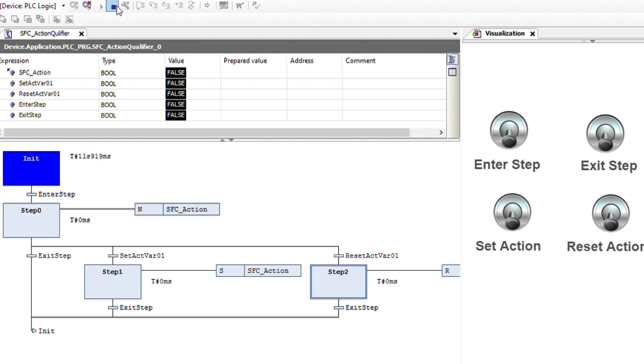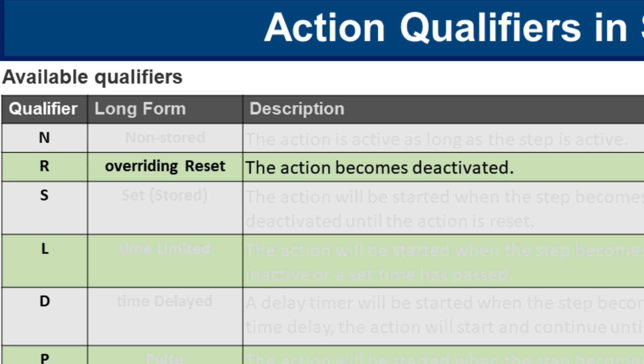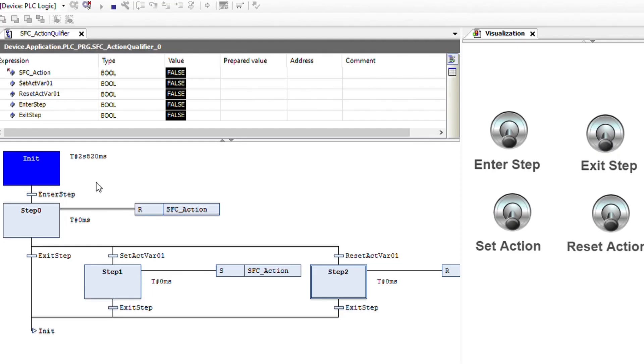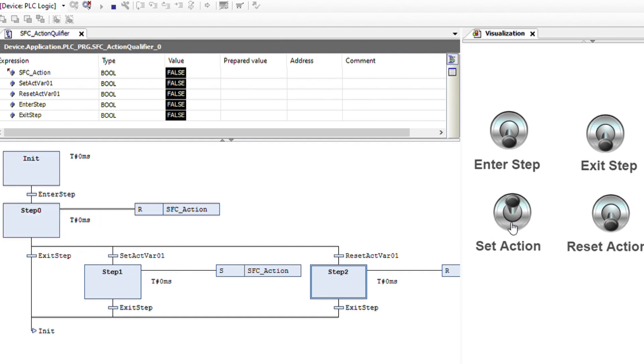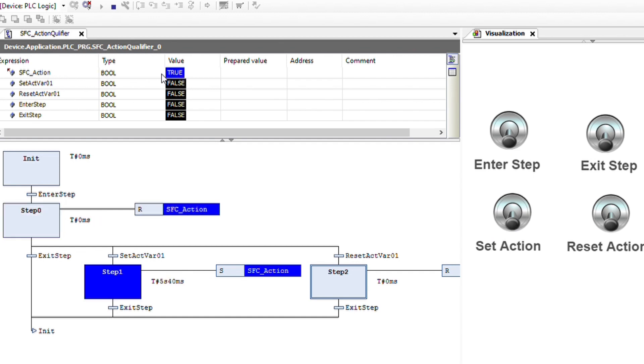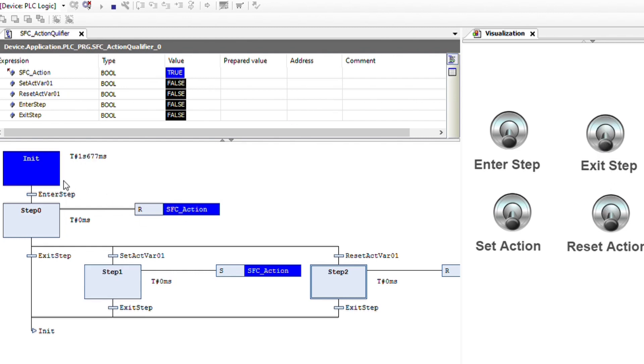Now let's switch to the next one. The next qualifier is R, and as you can see in the description, the action becomes deactivated — in other terms, the action will be reset. In Codesys, I change this qualifier to R. Initially the action itself is false. If we enter into the step, at that moment the action will be reset, and since it is already false, nothing changes. But if I set the action through here, now you can see that SFC action boolean variable is true. And if I go out and enter into step 0 again, as soon as I enter, the action will be reset. That's the way the R qualifier works.